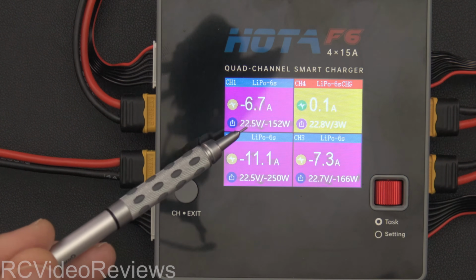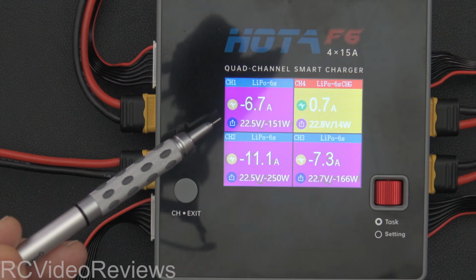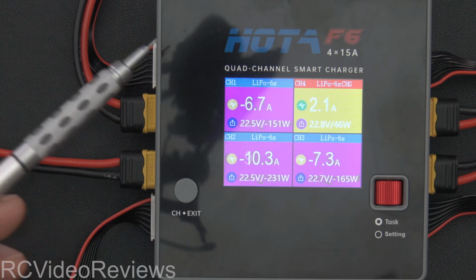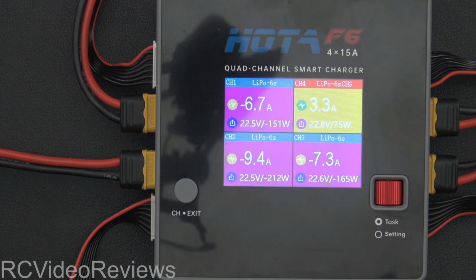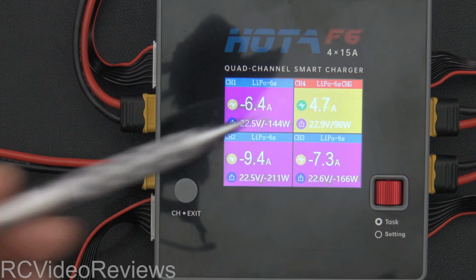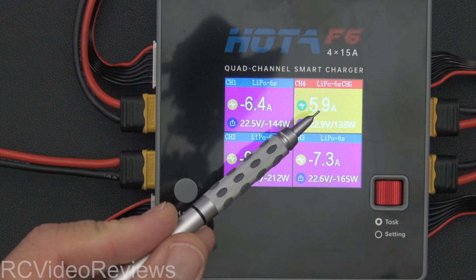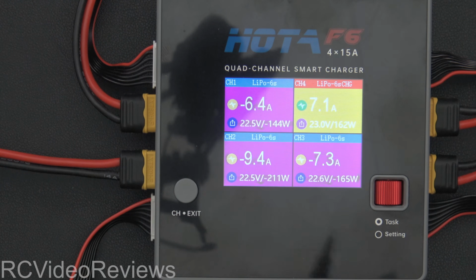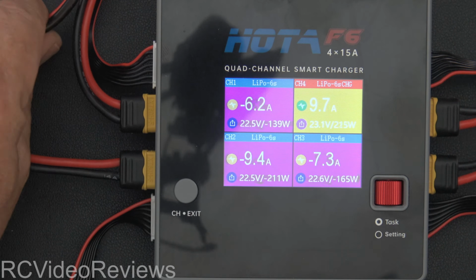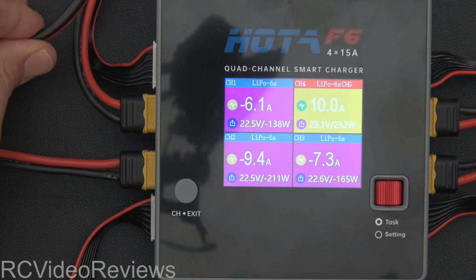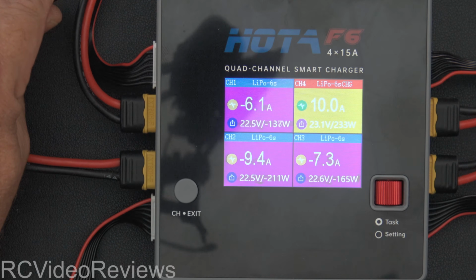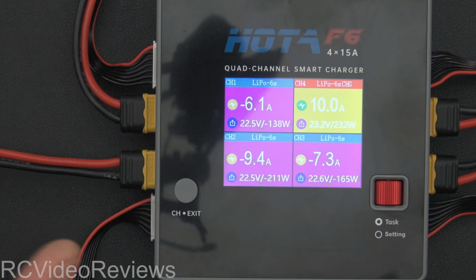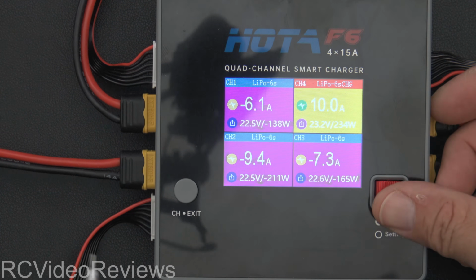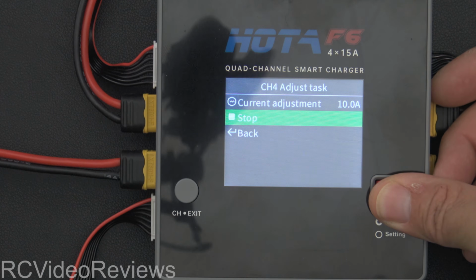Now we've got, you know, 14 amps, 24 amps, give or take, going into the battery bank, and another 5, it'll be 10 amps eventually coming back out. So pretty cool. Yeah, you can charge and discharge on the same settings at the same time simultaneously. And there's the lead going into my battery. I'm just holding that for temperature and checking the temp to make sure it's not getting too hot because we're moving a lot of current right now, but that's not bad. Not bad. Pretty cool little feature set. I like it. I'm digging that.